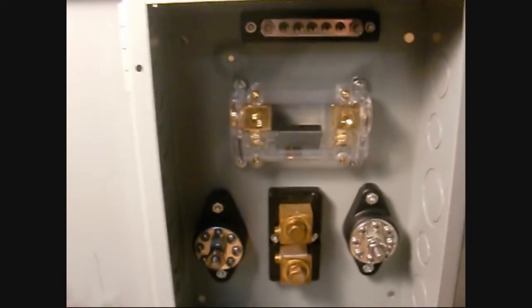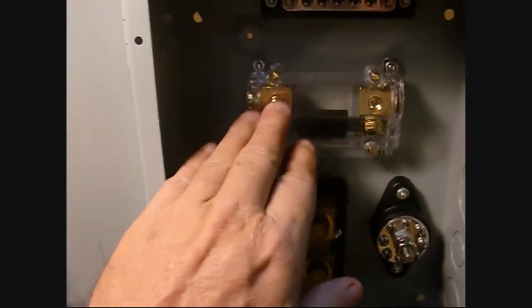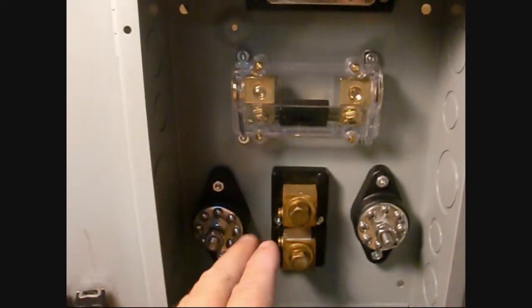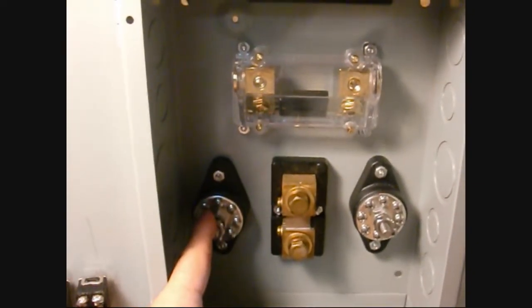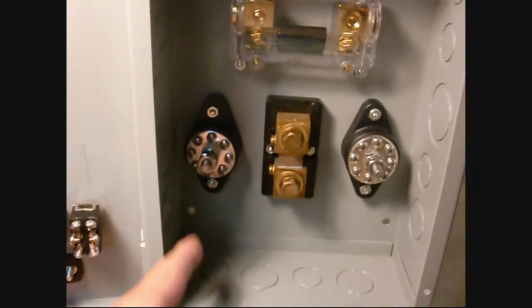I come back from the charge controller to go through this fuse, a slow blow fuse, down to this positive bus bar. The battery cable from the battery bank will also come up to this positive bus bar.